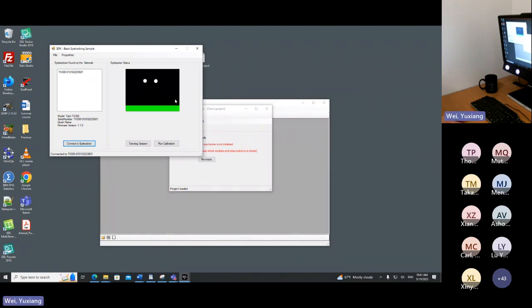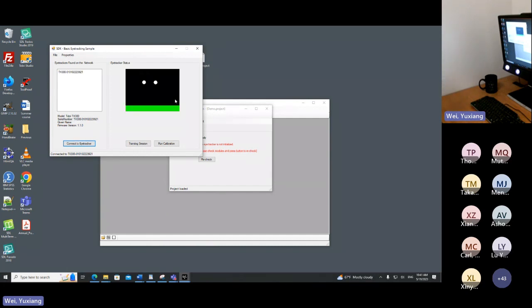We need to position participants correctly. If I move — say the chair is too high — the eye data will be lost. At the bottom we see a bar that shows a green color. If I move away from the eye tracker the data starts getting lost and the bar becomes red. If I approach too closely it also becomes red. We want the bar to be green, which indicates the distance between the eyes and the eye tracker is appropriate.